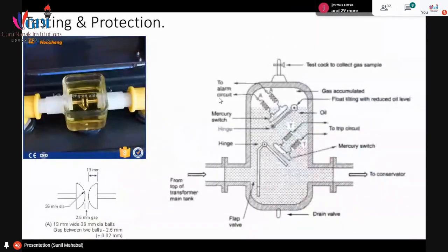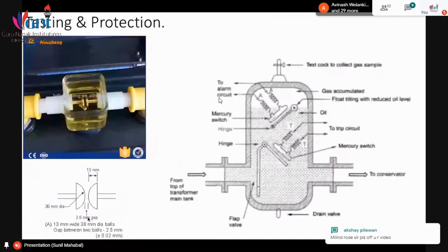Okay. Then this is how the testing and protection is done. You must be knowing that there are 36 mm diameter balls, and the distance between them is 2.5 mm. Then, with the help of a dimmer, the voltage applied across these two balls is increased. If it is an 11 kV transformer, then it will be increased beyond that. And it will be seen at what voltage it trips or creates the spark. That voltage will decide the dielectric strength of that oil.